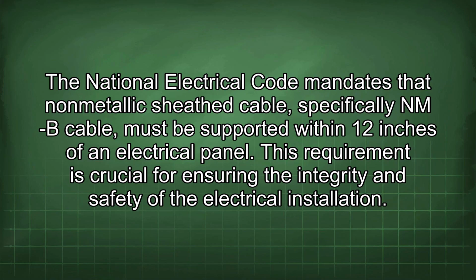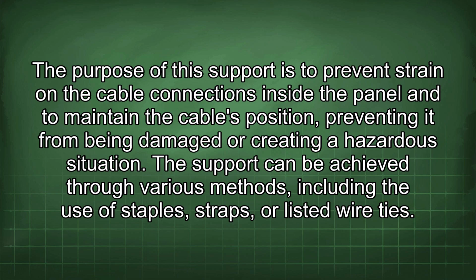The National Electrical Code mandates that non-metallic sheath cable, specifically NMB cable, must be supported within 12 inches of an electrical panel. This requirement is crucial for ensuring the integrity and safety of the electrical installation. The purpose of the support is to prevent strain on the cable connections inside the panel and to maintain the cable's position, preventing it from being damaged or creating a hazardous situation.